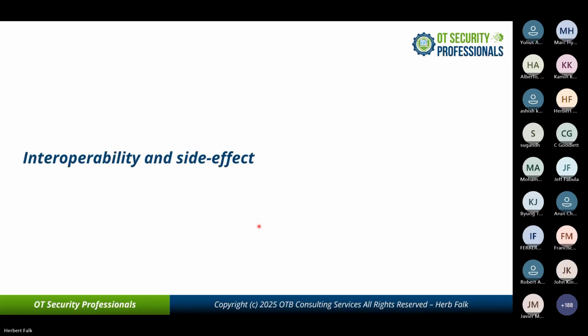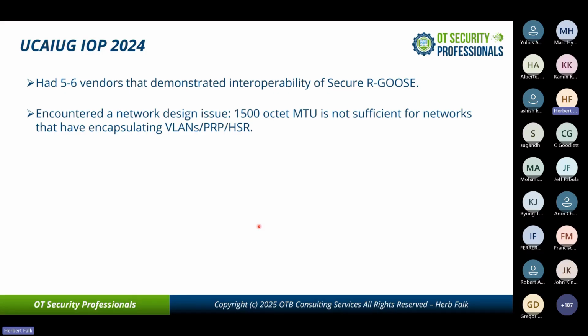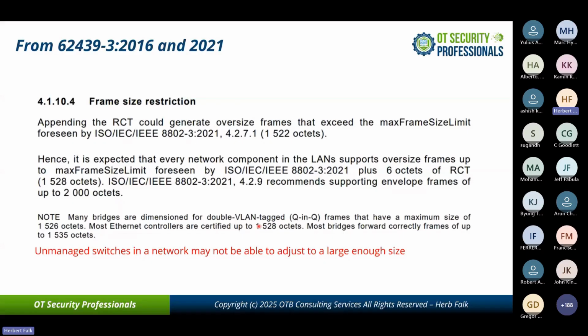Interoperability and side effects. We had 5 to 6 vendors that demonstrated interoperability of secure R-GOOSE, but we encountered a network design issue with the 1500 octet MTU. It's not sufficient for networks encapsulating VLANs, PRP, or HSR. This was a bugger to debug and find the root cause. Then you find out that 62439 already acknowledged this. What most people don't realize is when you're using VLANs, it's possible to encapsulate one VLAN in other VLANs and so forth, and you can rapidly exceed the 1522 octets.